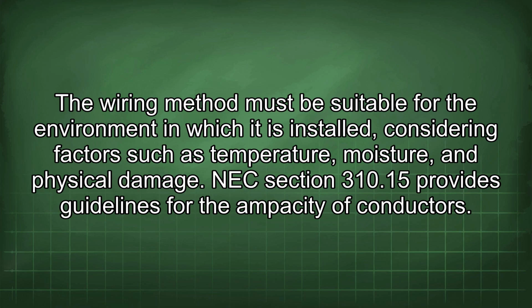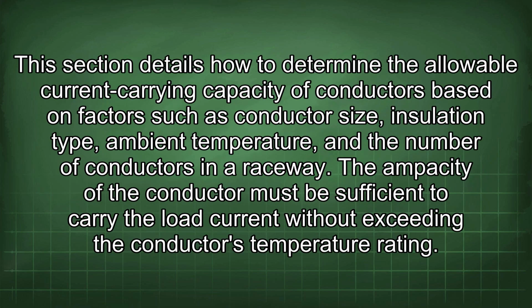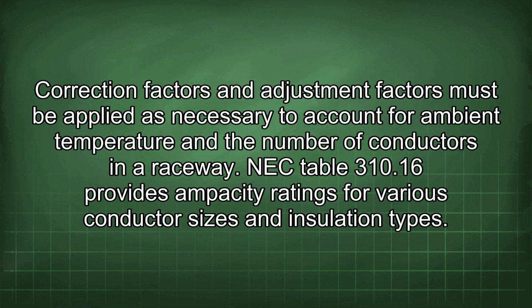and physical damage. NEC Section 310.15 provides guidelines for the ampacity of conductors. This section details how to determine the allowable current carrying capacity of conductors based on factors such as conductor size, insulation type, ambient temperature, and the number of conductors in a raceway. The ampacity of the conductor must be sufficient to carry the load current without exceeding the conductor's temperature rating. Correction factors and adjustment factors must be applied as necessary to account for ambient temperature and the number of conductors in a raceway. NEC Table 310.16 provides ampacity ratings for various conductor sizes and insulation types.